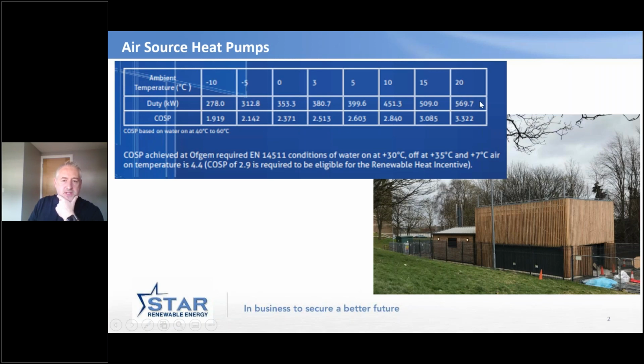we'll get 570 kilowatts of heat. If it's a -10 day, also quite rare in Glasgow, we'll get 278. Typical temperature in Glasgow actually varies between 0 and 10 degrees, 10 degrees being about the middle. So we would say this is around about a 400 kilowatt heat pump.